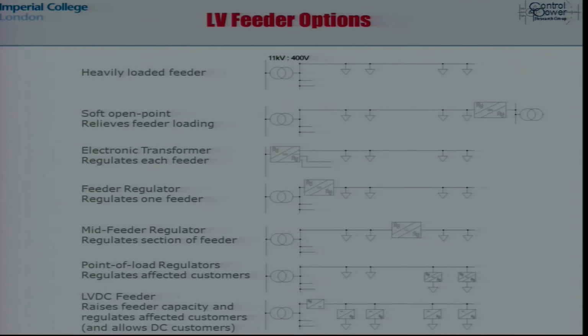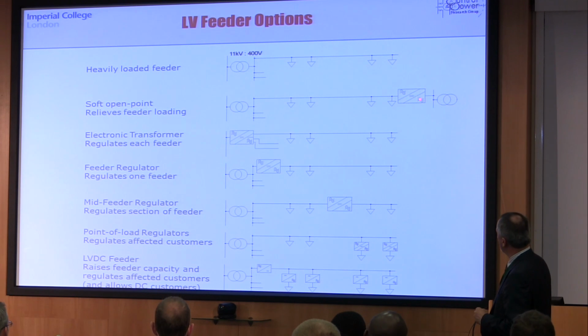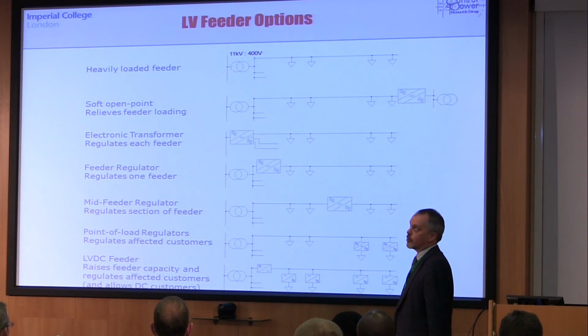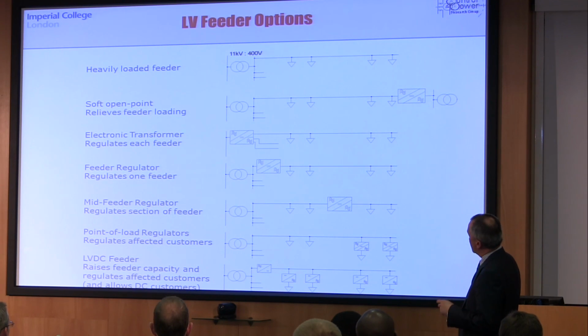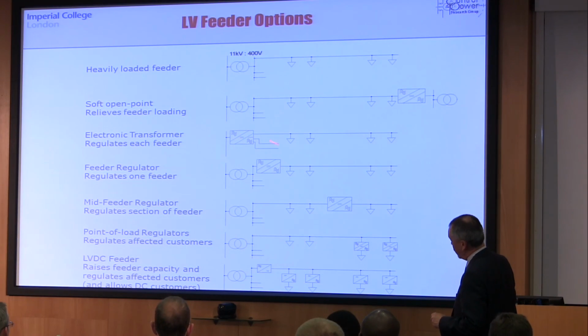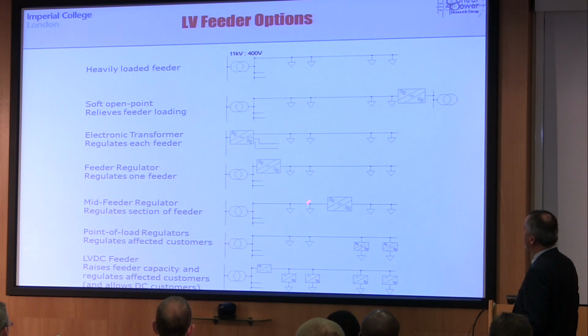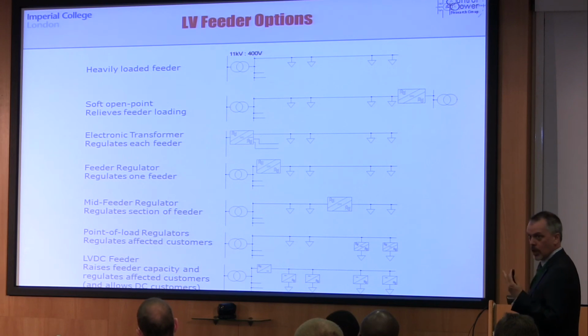So here were some thoughts just about what one might do on low voltage feeders. So the top diagram is just the reference point. It's a heavily loaded feeder with a substation up here which has no tap changer. So the first point maybe is if this point is low or high on volts, to put a soft open point, a back-to-back converter to a feeder on another substation. It relieves the feeder loading and could do that phase by phase, which is attractive. An often proposed solution is to actually replace the transformer with a fully electronic solution. So here, back-to-back converter arrangement, basically, but feeding the feeder so we can control the voltage at this point in a continuous fashion, unlike a tap changer, and perhaps have different feeders controlled differently, which would be attractive.